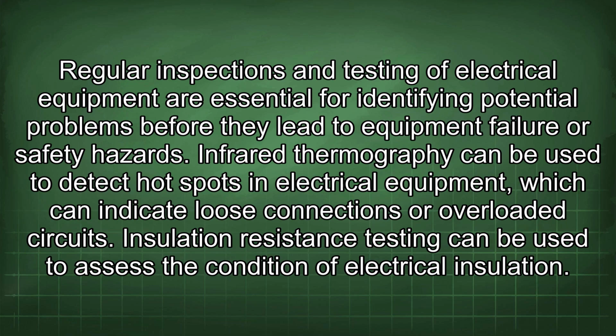Regular inspections and testing of electrical equipment are essential for identifying potential problems before they lead to equipment failure or safety hazards. Infrared thermography can be used to detect hot spots in electrical equipment, which can indicate loose connections or overloaded circuits. Insulation resistance testing can be used to assess the condition of electrical insulation.